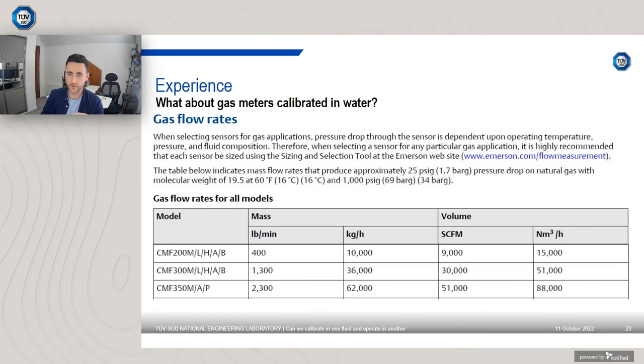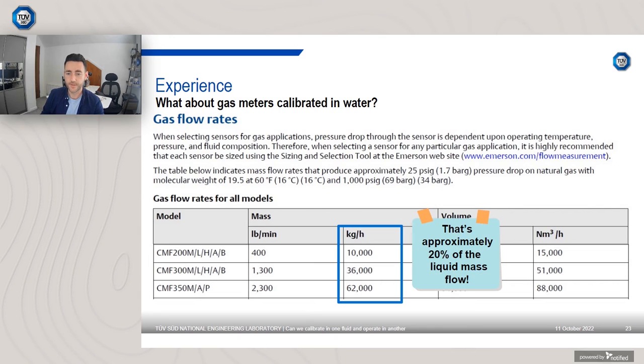Let's look at it in terms of gas. Once again, I've got my blue rectangle. So this is the same manufacturer, the same meters, 2 inch, 3 inch and 4 inch, the exact same devices. But you can see for mass flow, the nominal gas mass flow rate is a magnitude lower. So for that 3 inch meter, previously, if you remember, I said 160,000 was roughly the maximum nominal flow rate, or the nominal flow rate, apologies. For gas, it's 36,000 kilograms an hour. So that's significantly different. I've got a wee sticker here. It's approximately 20%. If you do the calculation, that's approximately 20% of the liquid mass flow rate.